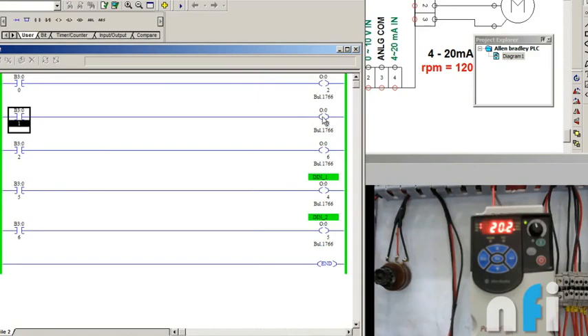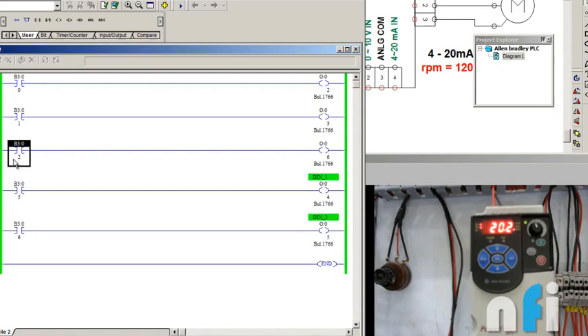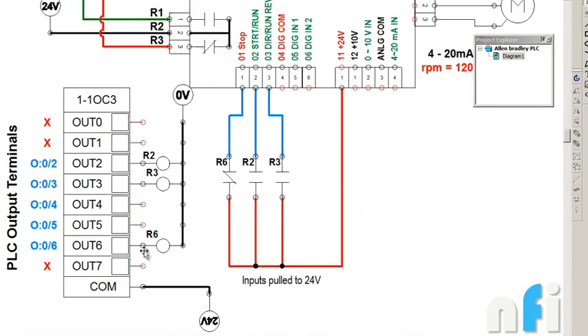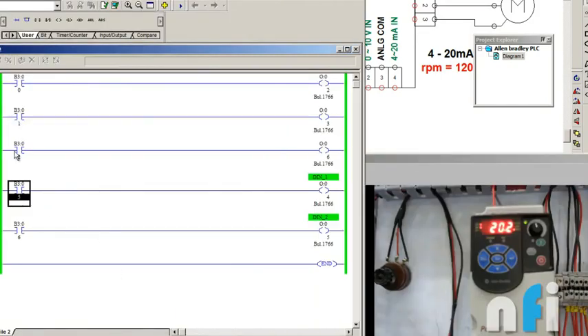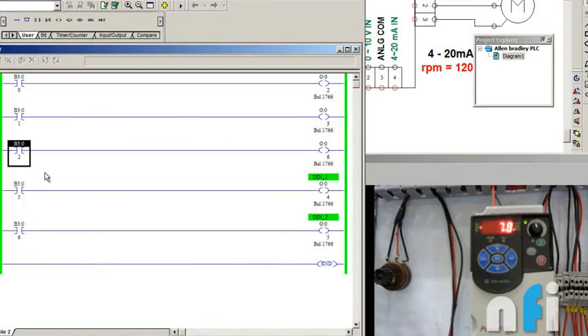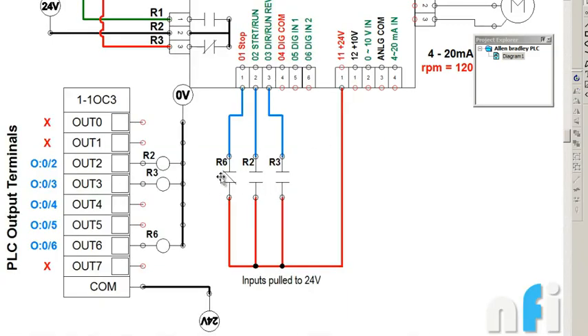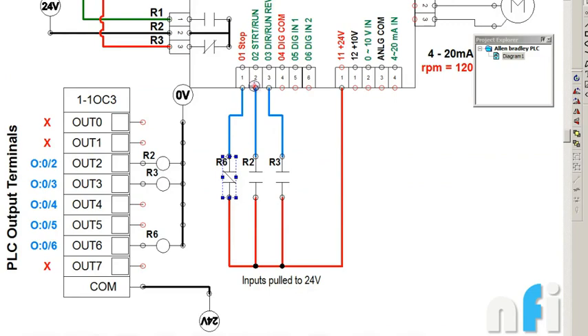Now let's stop it. To stop it I will just turn it once. So when I run this bit 2, it will turn on OUT6. When OUT6 is on, this is NC, this will be open. So when this opens, drive gets stopped. Let's see, this has stopped the drive. I have removed the switch, driver stopped. I'll explain again why it stopped. Because it needs constant supply of 11 and 1. Even when you purchase a drive, you'll find this wire is already connected. So we have done it using an NC contact. If this NC gets open, no matter what's happening, drive will stop.